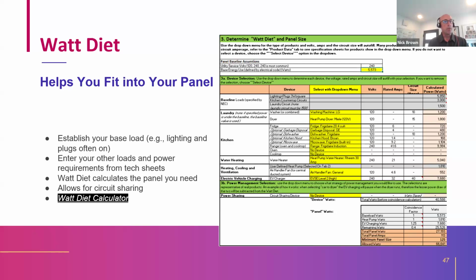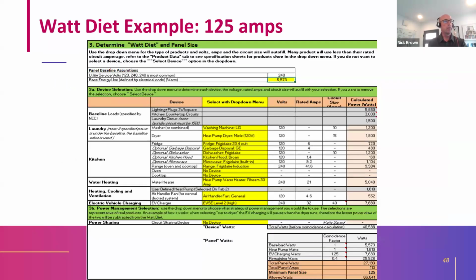It also has a part right above the final tally for power sharing. That's where you would put a device that would put multiple systems on a single circuit. The National Electric Code provides for only counting systems that are on shared circuits like that, with approved circuit sharing devices, once in the calculation. So that's one of our key tools to come in under an existing panel size. We'll show you some of those systems on the market for that coming up.